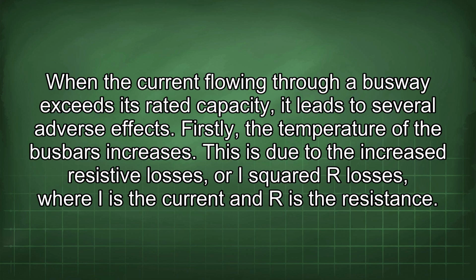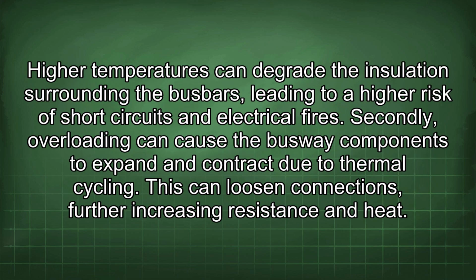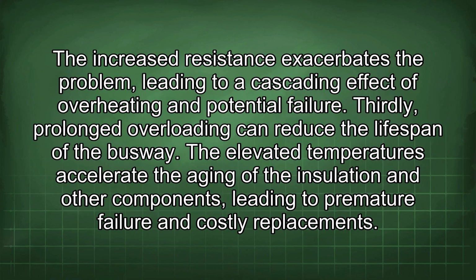Firstly, the temperature of the busbars increases. This is due to the increased resistive losses, or I²R losses, where I is the current and R is the resistance. Higher temperatures can degrade the insulation surrounding the busbars, leading to a higher risk of short circuits and electrical fires. Secondly, overloading can cause the busway components to expand and contract due to thermal cycling. This can loosen connections, further increasing resistance and heat. The increased resistance exacerbates the problem, leading to a cascading effect of overheating and potential failure.